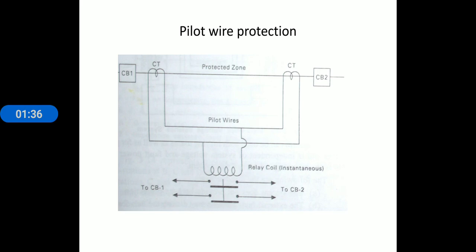See here, once again I'm explaining it. This figure is a general schematic diagram for pilot wire protection, or differential pilot wire protection. It works on a simple principle. Under normal conditions, the entering current of this line is equal to the leaving current of this line. At that time, no differential current flows through this relay.